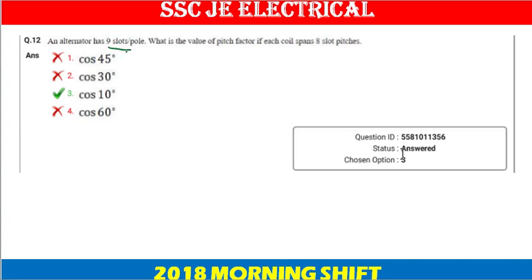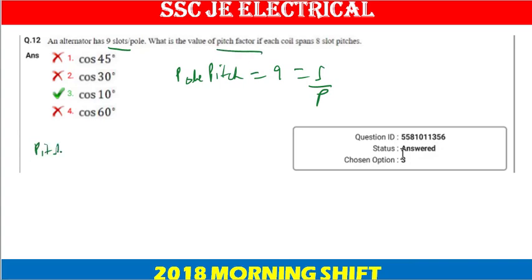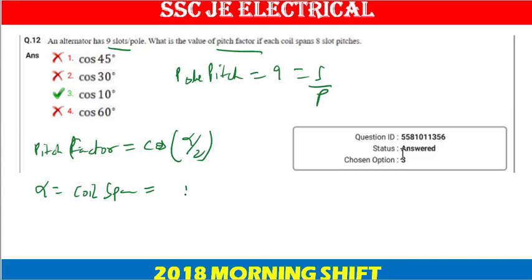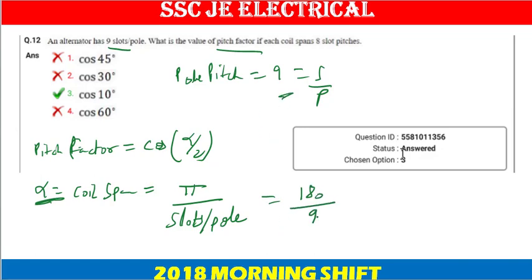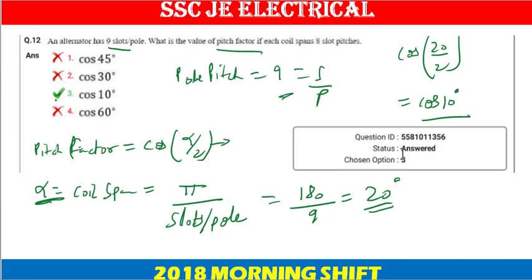Next question: an alternator has 9 slots per pole. Pole pitch equals 9 slots per pole. We need to find the pitch factor. Pitch factor equals cos(alpha by 2), where alpha is the coil span in electrical degrees. Coil span equals 180 divided by slots per pole equals 180 divided by 9 equals 20 degrees. So pitch factor equals cos(20/2) equals cos 10 degrees. Answer: option C.